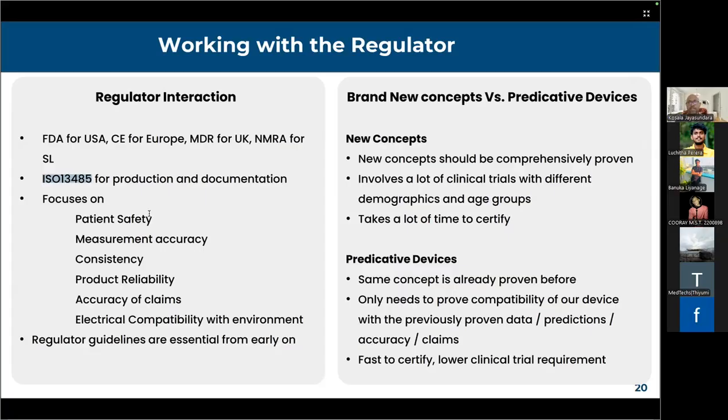That's a huge issue because that's based on the patient's reading accuracy, which the doctors are using to diagnose the patient. For that kind of thing, the factory should make sure that raw material input is consistent and they are testing 100% of output, and they are rigorously testing a certain percentage of the products, which is again specified by the FDA and MDR based on the risk levels, to make sure that the product doesn't have deviations like that.